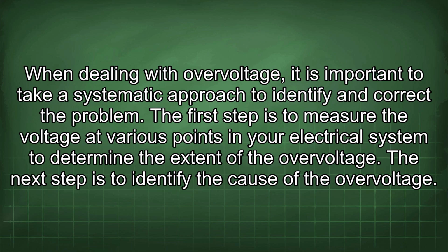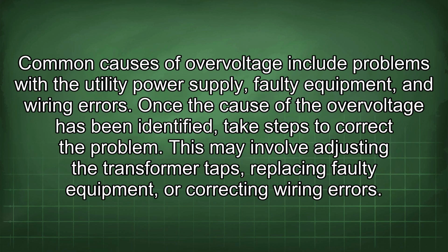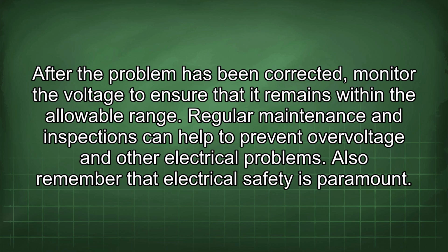When dealing with overvoltage, it is important to take a systematic approach to identify and correct the problem. The first step is to measure the voltage at various points in your electrical system to determine the extent of the overvoltage. The next step is to identify the cause of the overvoltage. Common causes of overvoltage include problems with the utility power supply, faulty equipment, and wiring errors. Once the cause of the overvoltage has been identified, take steps to correct the problem. This may involve adjusting the transformer taps, replacing faulty equipment, or correcting wiring errors. After the problem has been corrected, monitor the voltage to ensure that it remains within the allowable range. Regular maintenance and inspections can help to prevent overvoltage and other electrical problems.